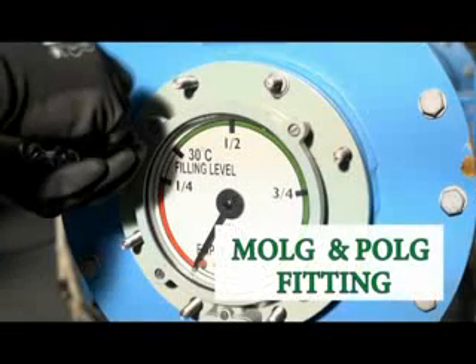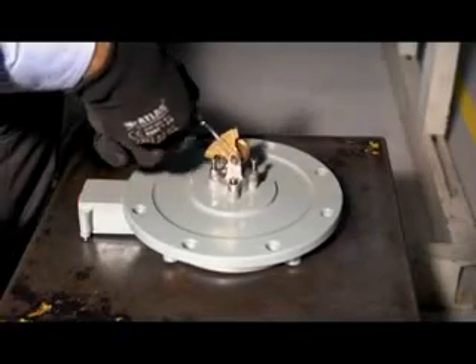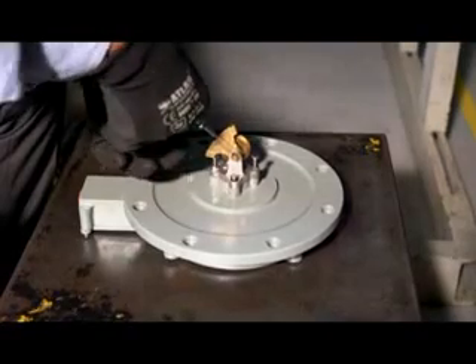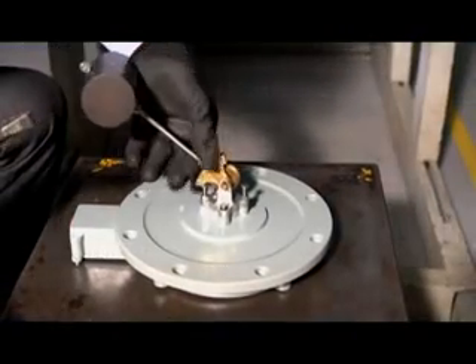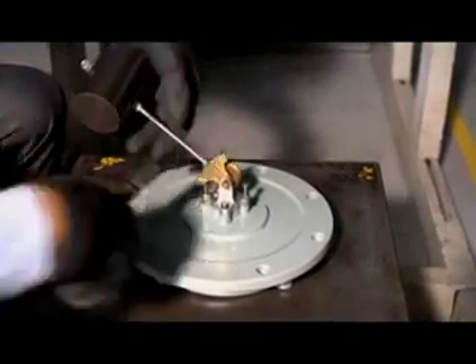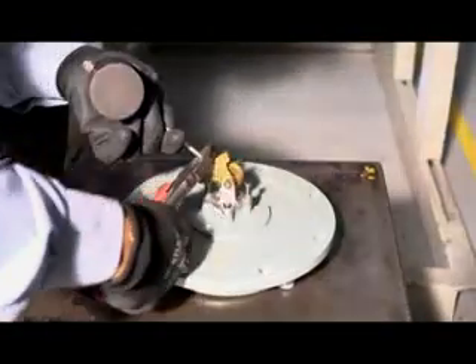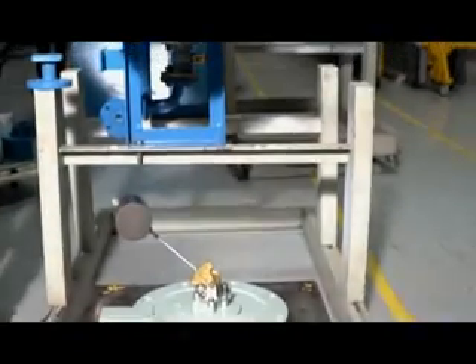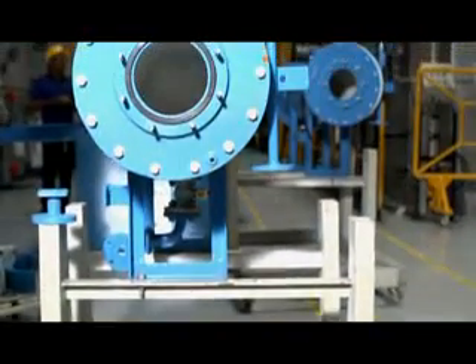MOLG and POLG, magnetic oil level gauge and prismatic oil level gauge fitting. MOLG shows the level of the oil in the conservator tank through the needle as a clock, and it's connected through a float that is moving inside the conservator tank, and it moves accordingly. And it moves according to the level increase or decrease in the conservator.